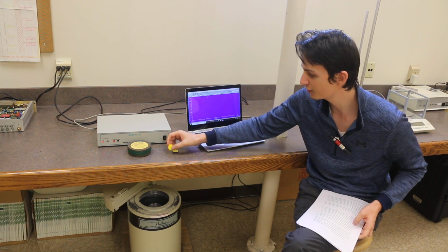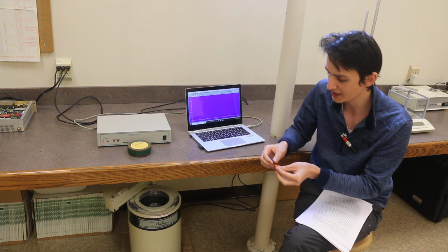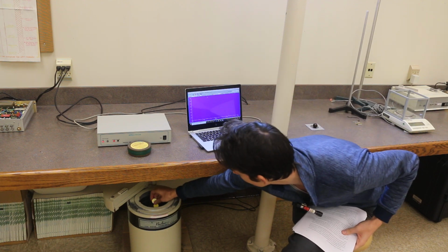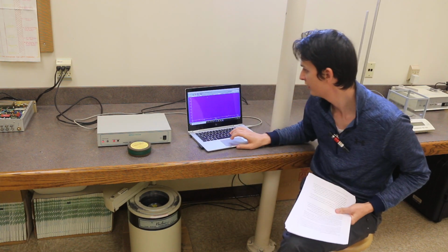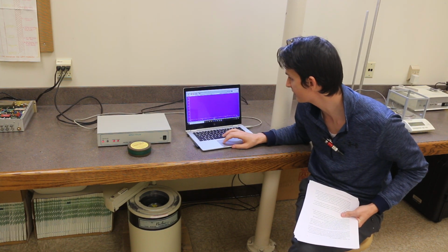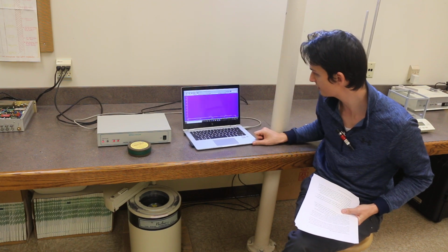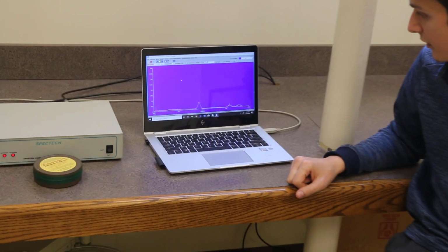So in order to calibrate that correctly, we will be using something that you are familiar with, which is our cobalt 60 and cesium 137. So we'll go ahead and put those on the crystal here. Now we did have to fiddle with the voltage, the coarse gain, and the fine gain to make sure our peaks looked correct. And so we're starting our collection here.